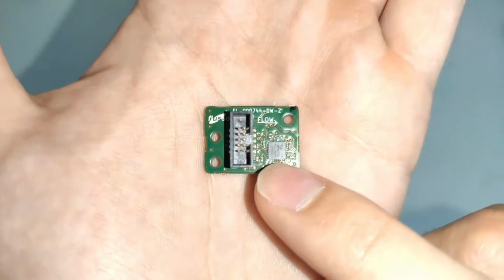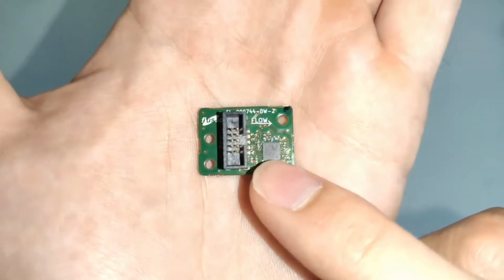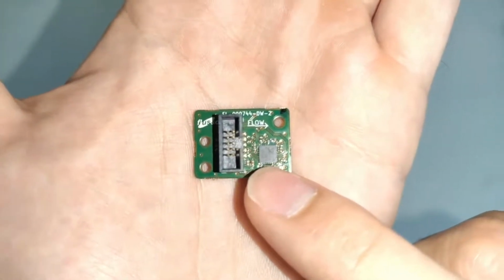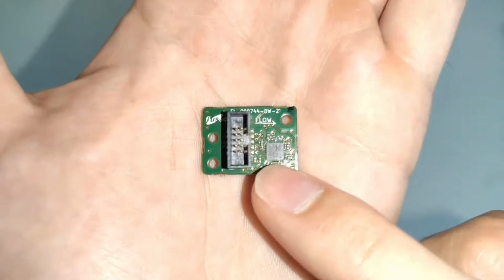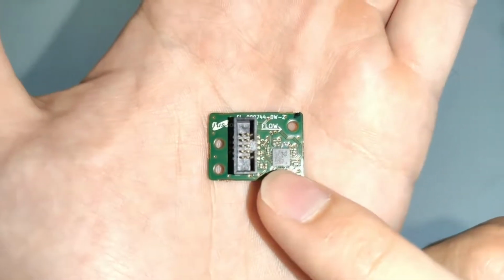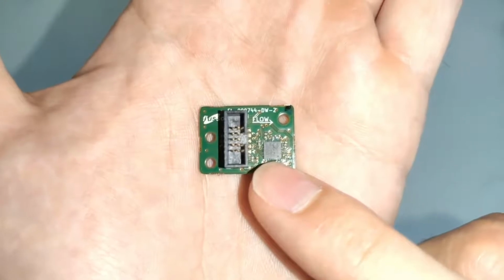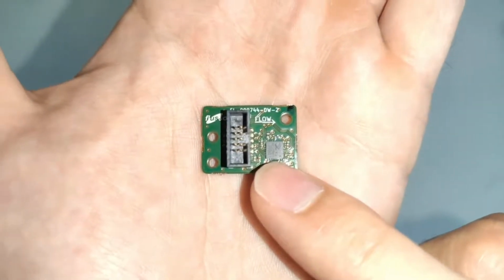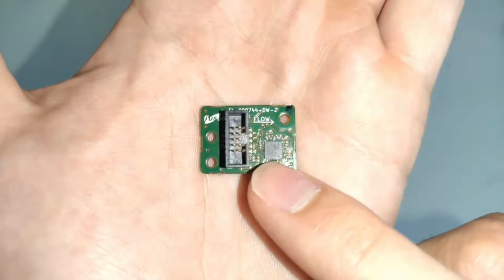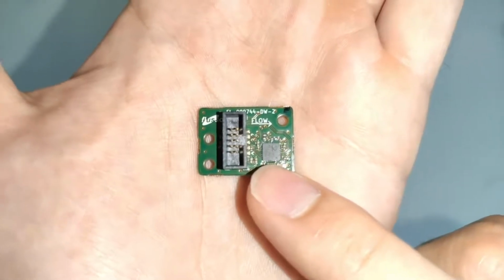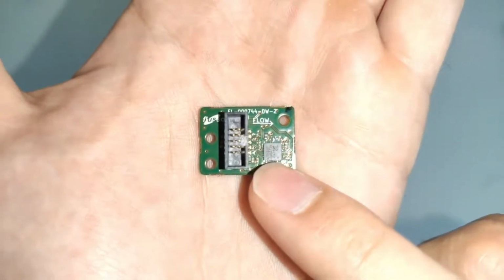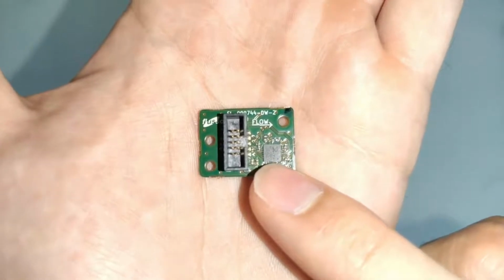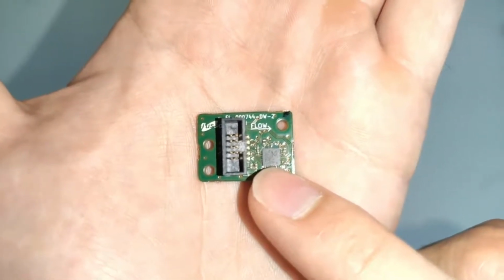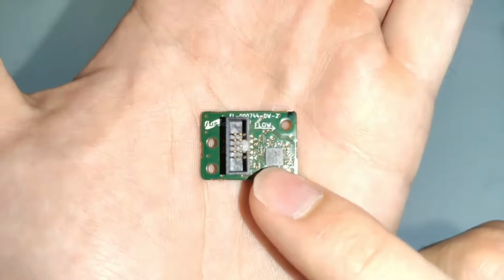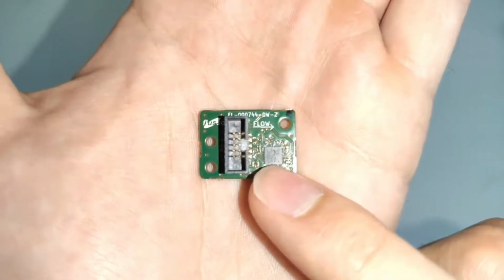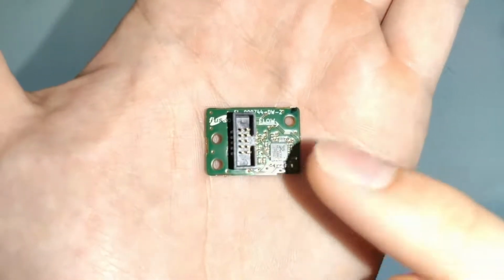You can also see there's a small microcontroller on this side of the board. This is an STM32 Cortex M0 core microcontroller, and it's responsible not only for driving the FLS110 sensor, but also reading the analog signals from the sensor and performing all the calculations necessary to convert those signals into a fully temperature and pressure compensated flow, differential pressure, or airspeed measurement.